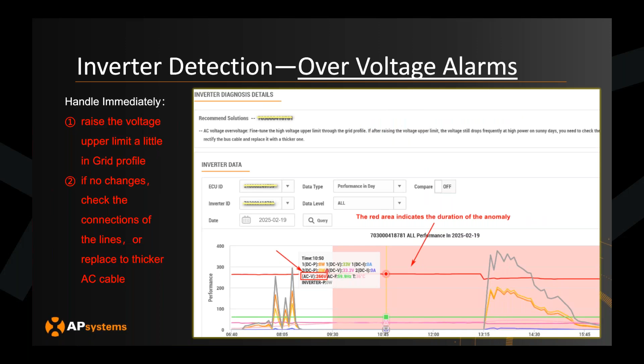Step by step: thicker wire has lower resistance, and with lower resistance, the voltage increase from point A to point B is smaller, because I times R equals the voltage rise. So with a smaller R and the same I, V also gets smaller. That's why voltage rise calculations are important, to make sure the right wire thickness is used to accommodate the voltage rise effect. So to summarize, if you see high AC voltage, call our tech support and we can increase the AC parameters of the inverters. But if that's not possible and the AC voltage goes too high, the other option is thicker AC cable for less voltage rise.